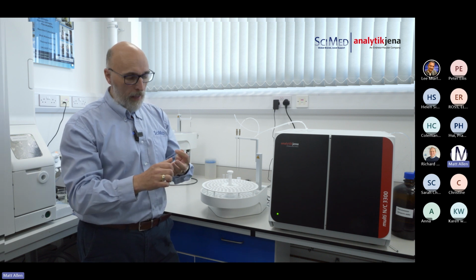Okay, so the sample is being injected by one or other of the different auto-samplers, and they all have different injection volumes. So the 33 and the 43 are pretty similar. You can normally go from 100 microliters up to 1 mil quite easily. There is a high sensitivity version that allows you to go up to 3 mil injection, and there's even a special pharma version that allows you to go up to a 20 mil injection. But most people are working around about half a mil.